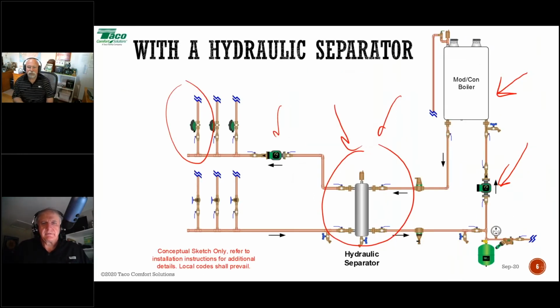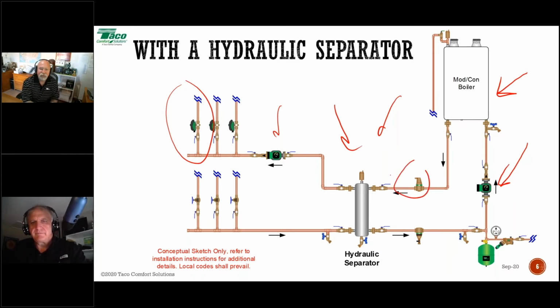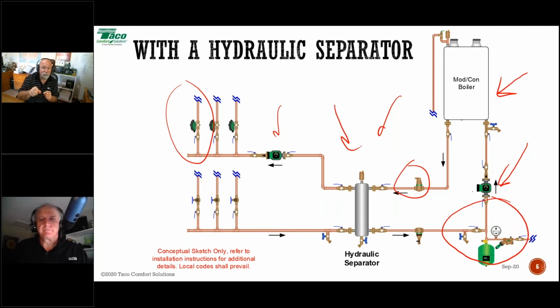Yeah, one fellow was asking about the location. I'm trying to point. One fellow was trying to ask about the location of the air separator and why we weren't pumping away from that. So I answered the question, but go ahead and reemphasize. A lot of people will see the expansion tank hooked to the bottom of the air separator, and they always think, "Oh, pump away." What they're forgetting is that we're pumping away from the point of no pressure change, which is where the expansion tank meets the system. So in this case, notice how John just circled that. We are pumping away.